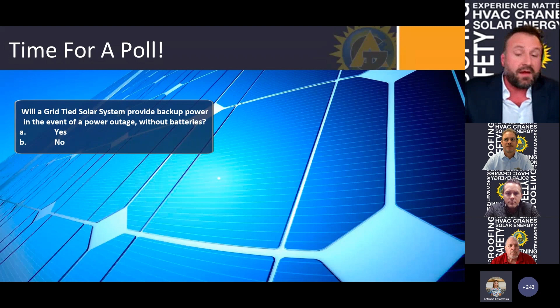A true grid-tied solar system, without any sort of microgrid controller or battery backup system, actually cannot provide power in the event of an outage. The UL listing requirements for our grid interactive inverters require that they shut down within a fraction of a second if they lose the utility grid reference they're matched up to. That's a safety requirement for life safety. But with the use of automatic transfer switches or motorized breakers and a battery bank, we can create what we call a microgrid that isolates us from the utility grid, and we're able to provide that power.